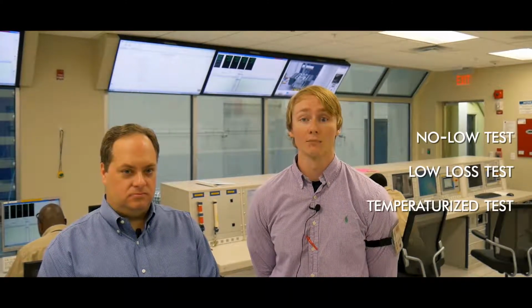Our next tests range up to our high voltage tests, which include no load tests, load loss tests, and our extensive temperature rise tests that can last anywhere from 2-4 hours all the way up to 72 hours or even longer durations of time.